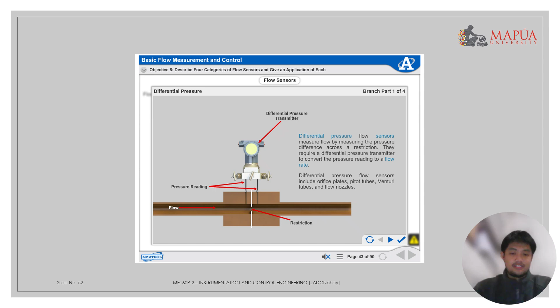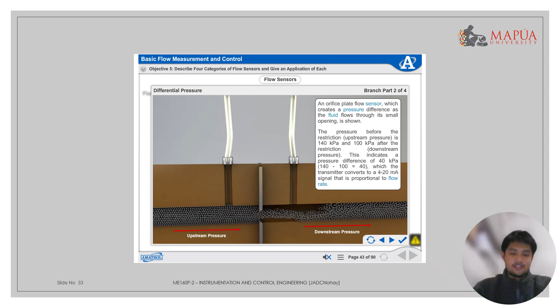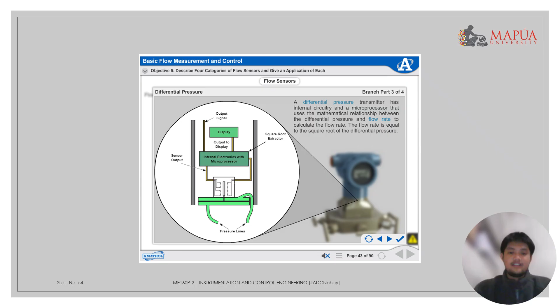An orifice plate sensor, which creates a pressure difference as the fluid flows through its small opening, is shown. The pressure before the restriction, upstream pressure, is 140 kPa, and 100 kPa after the restriction, downstream pressure. This indicates a pressure difference of 40 kPa, which the transmitter converts to a 4 to 20 milliamp signal that is proportional to flow rate. A differential pressure transmitter has internal circuitry and a microprocessor that uses the mathematical relationship between the differential pressure and flow rate to calculate the flow rate. The flow rate is equal to the square root of the differential pressure.